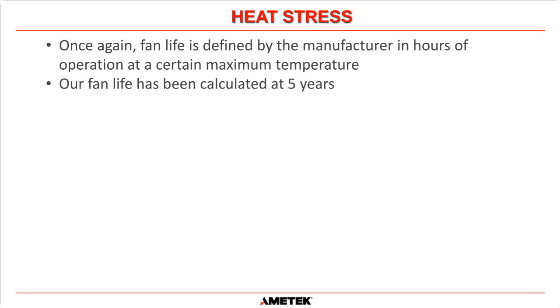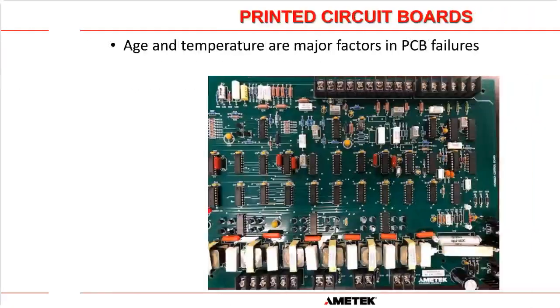And obviously fans have motors and they have lifespans. Once again, the manufacturers of fans list their life in hours based on many different specs. We looked at these specs, and our fan life has been calculated at about 5 years. So we always recommend that the fans inside our systems are replaced every 5 years to make sure that the airflow is always maintained, and therefore all of the electronics within that UPS cabinet are not being subjected to heat stress, which, as we saw, causes up to 50% of all electronic failures. So it's a very important thing to make sure your fans and your fan motors are maintained.